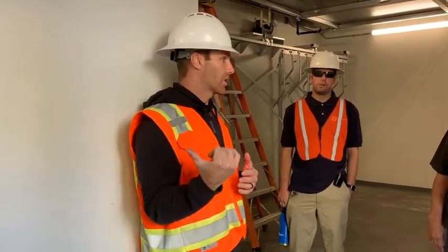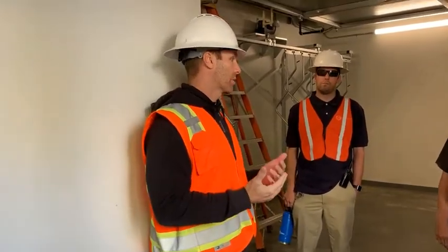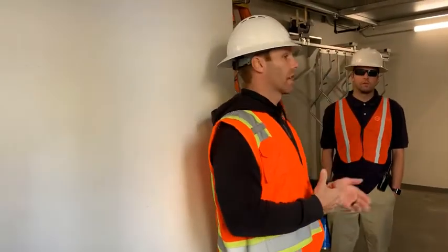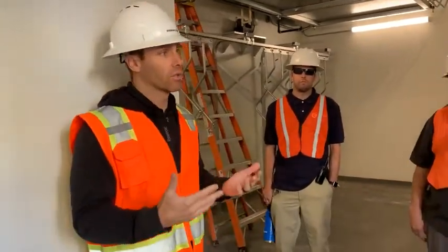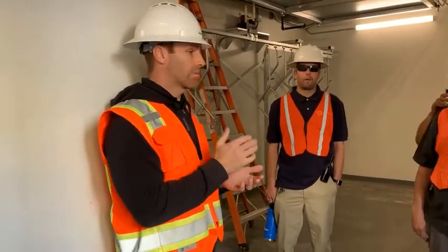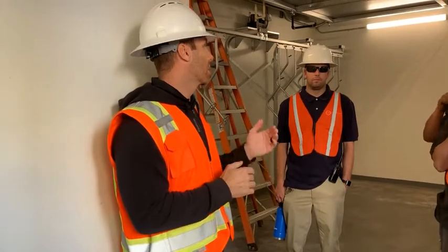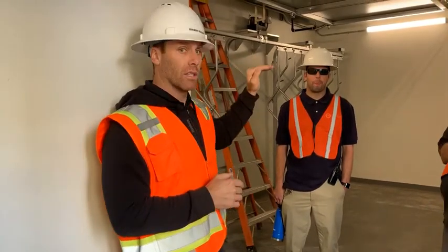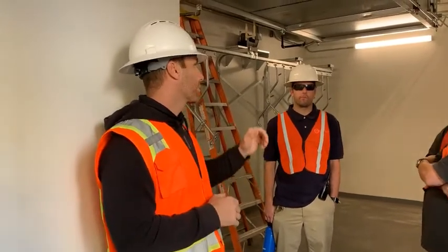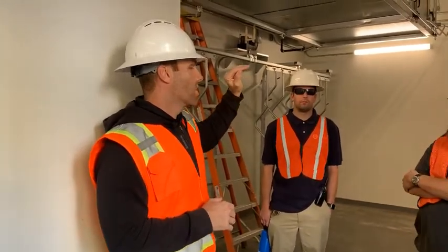So the Eclipse right there is usually just doing exterior lighting or any type of time schedule you may have. When I say time schedule, that's not referring to the time delay on an aux sensor. The aux sensor, usually we set it to 10 minutes. It's inherent in the device. We can change it to 5, 20 minutes, whatever we want to do. But typically our aux sensors are at 10 minutes. They have a dim warning at 7.5. Basically, that would work no matter if it was actually attached to Eclipse or not, okay?